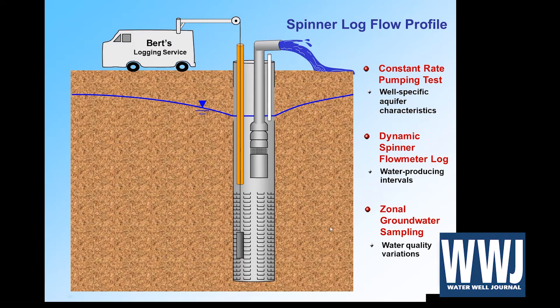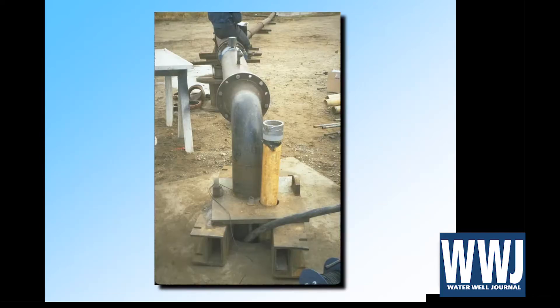For example, we might have a well with a little bit of high nitrate in the upper part of the aquifer. Where do we run a liner or two? We could just guess and maybe not get rid of all the nitrate or even lose too much water production. But here we would know what we're doing ahead of time, and it's not too expensive. Here's how it looks when you set it up: the submersible pump is down the well, we have the electrical cable, the sounding tube in the middle, and the PVC access tube. Pretty straightforward setup.